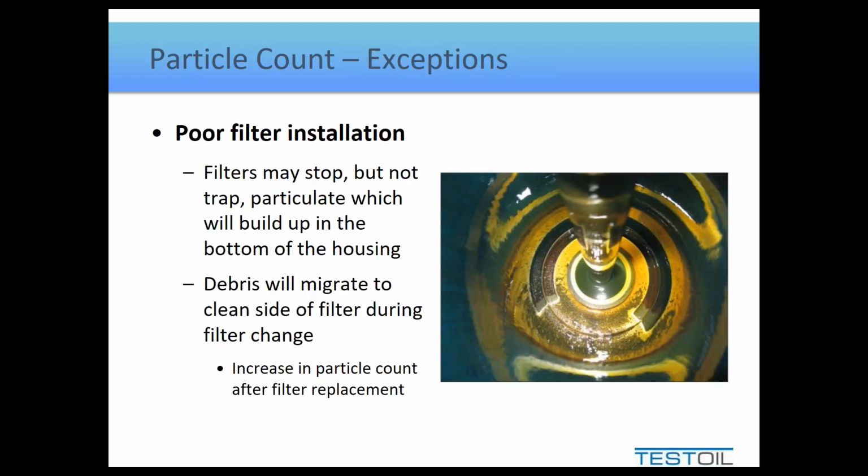Now, when you remove a filter without having fully drained the housing, what happens is the oil has to displace itself to fill the void where the filter was. So when you pop that filter off the bottom of the filter housing, oil from both sides, clean and dirty, rush to fill that little void.